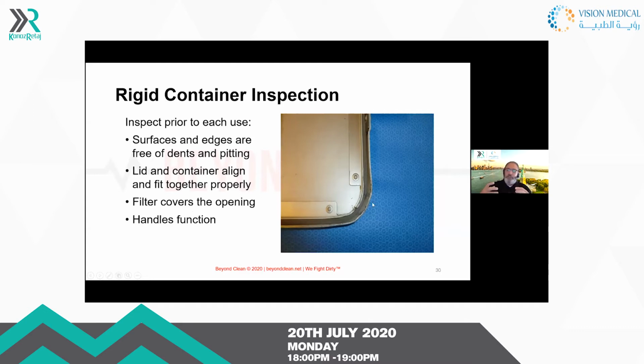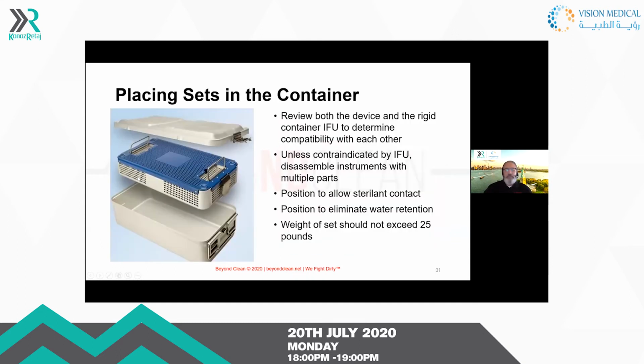So this can impact the sterility of that device for sure. So we want to make sure that we're taking care of that. As you move to loaner instrumentation, always remember that before you stick the loaner tray into a sterilizer, you want to ensure that the manufacturer of the instruments and the manufacturer of the container have worked together to make sure that this device is validated.